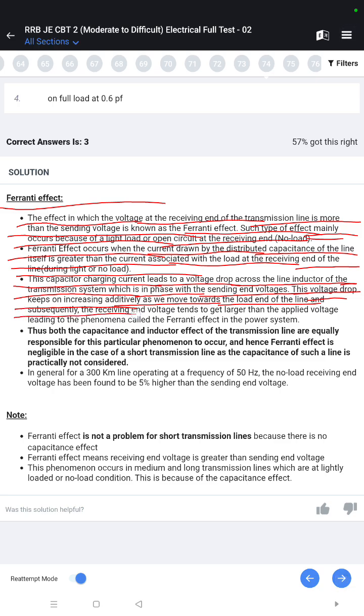This capacitor charging current leads to a voltage drop across the line inductor of the transmission system, which is in phase with the sending end voltage. This voltage drop keeps on increasing additively as we move towards the load end of the line, and subsequently the receiving end voltage tends to get larger than the applied voltage, leading to phenomena called the Ferranti effect in power system. Thus, both the capacitance and inductor effect of the transmission line are equally responsible for this particular phenomenon to occur, and hence Ferranti effect is negligible in the case of a short transmission line, as the capacitance of such a line is practically not considered.